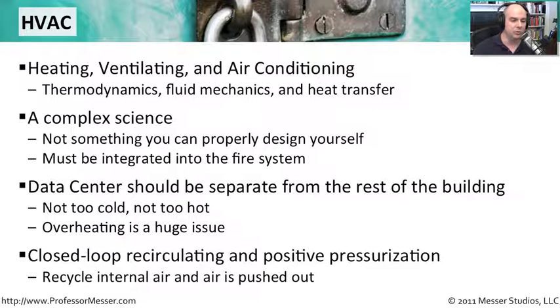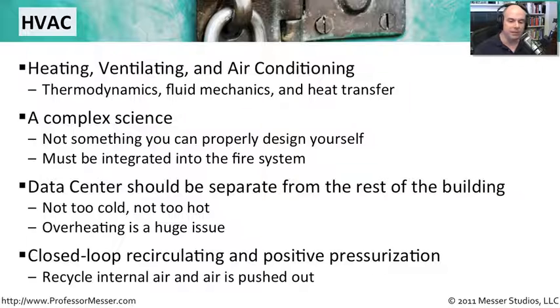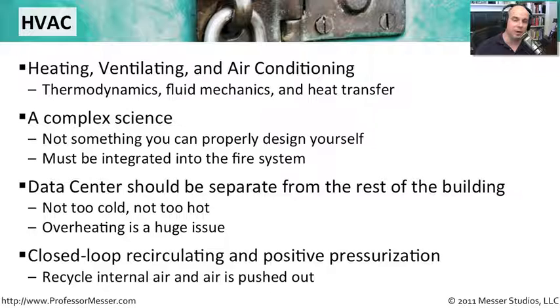These are systems called closed loop recirculating systems, and they're also called positive pressurization systems — you'll see those referred to when you look at HVAC. In a closed loop recirculating system, the internal air within your organization is constantly being recirculated; you're not pulling air in from the outside. Positive pressurization means that if you open the door to your building, air is going to rush out. That's exactly what you want, especially when air is being filtered — you don't want unfiltered air coming inside. And in the case of fire or smoke, if somebody opens the door, positive pressurization will push everything inside out.